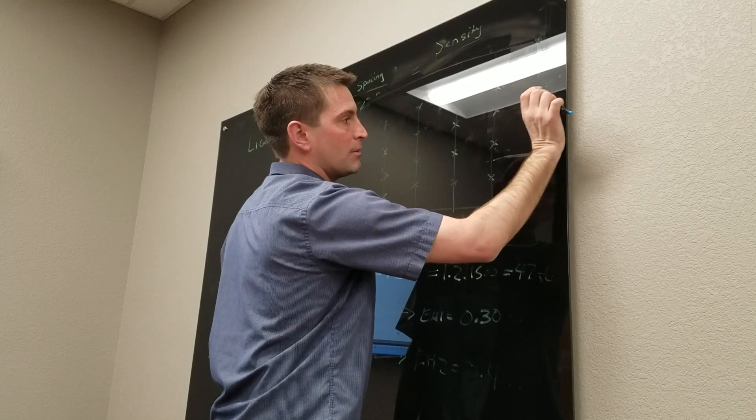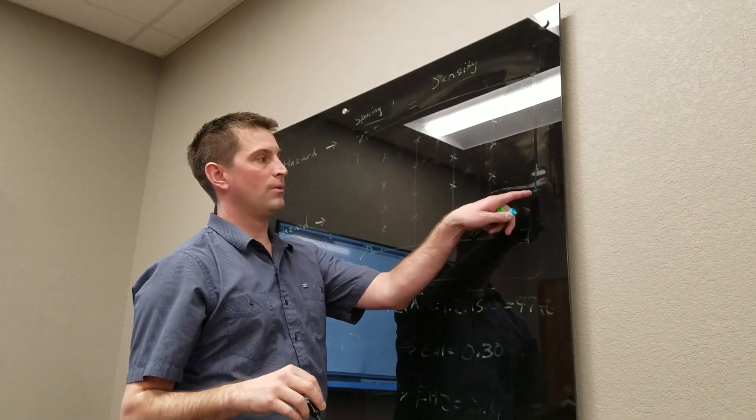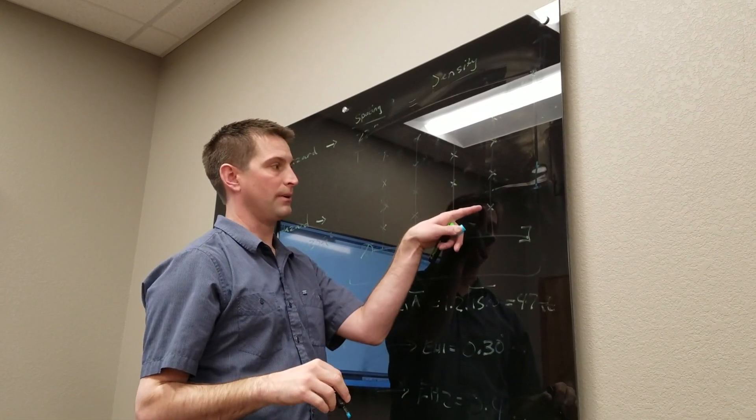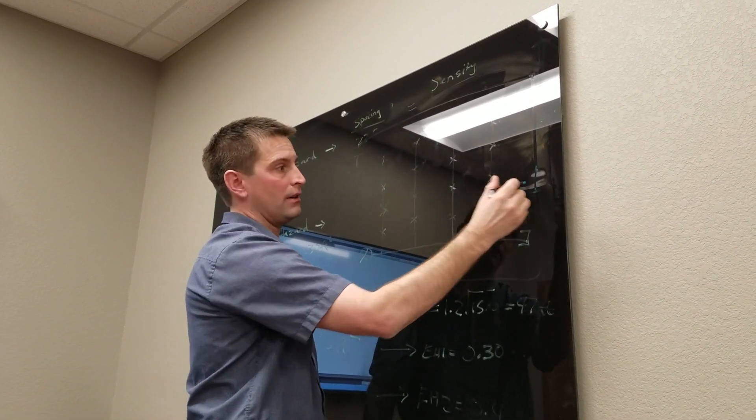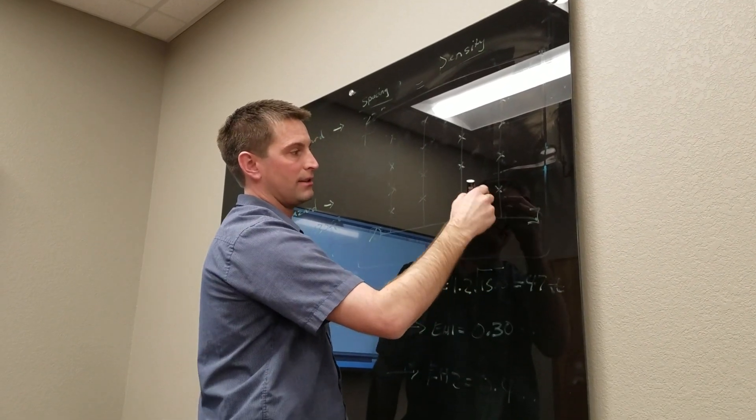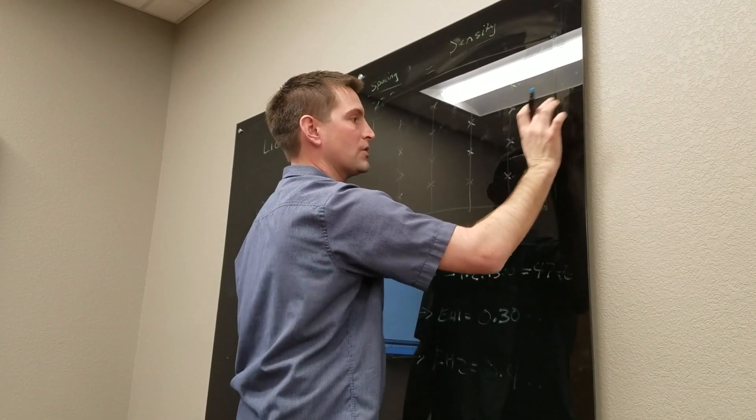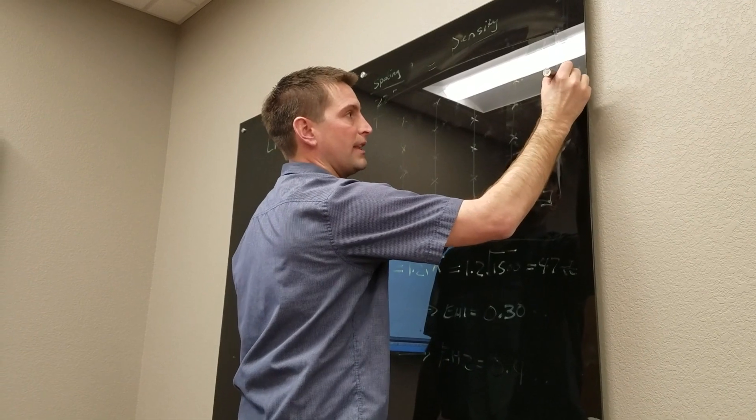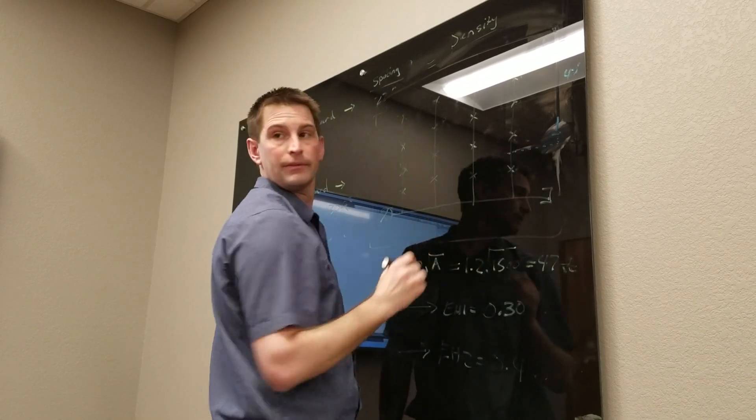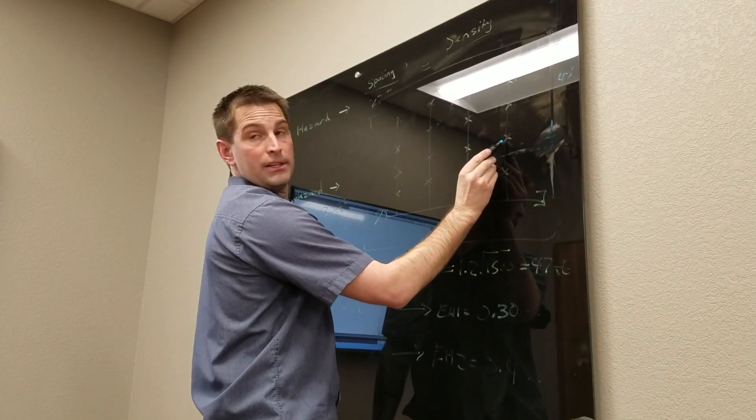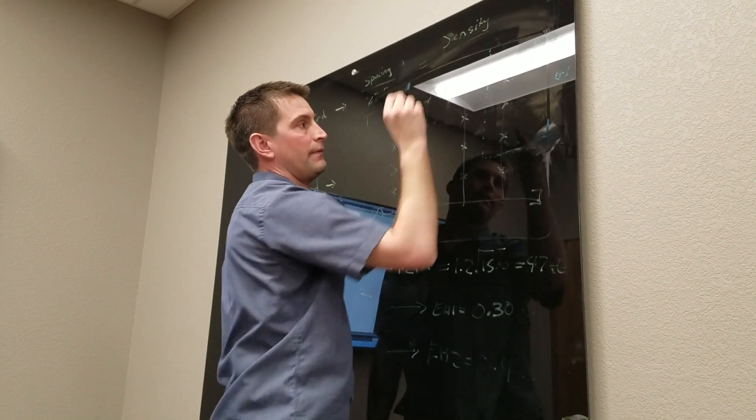If 47 was to put me there, a little bit past that halfway point, now where's that put me? Protection area of which sprinkler? This one. So because it's into this one, now I have to pick up that whole sprinkler. Let's just go back because of my picture here. So let's say that 47 put me just short of the halfway point. This head protects halfway between two, right? So I would go halfway and I would go halfway. That would be my remote area.